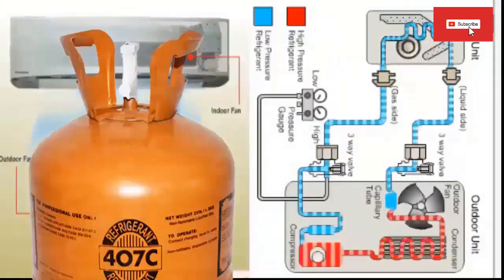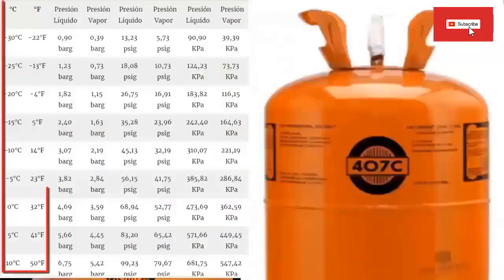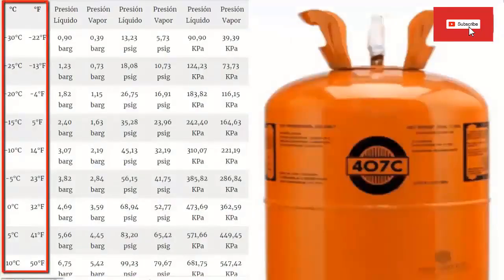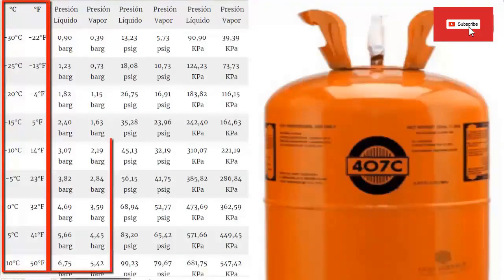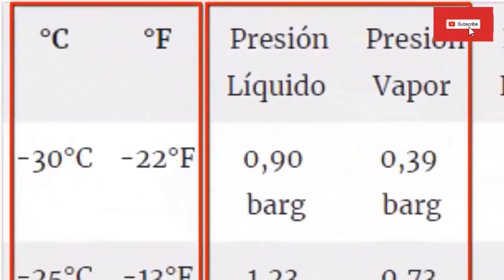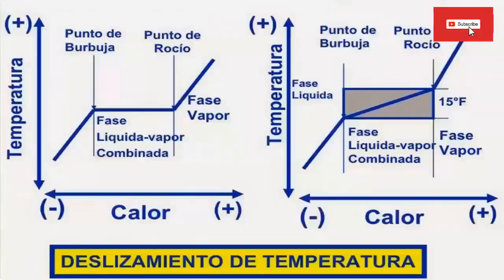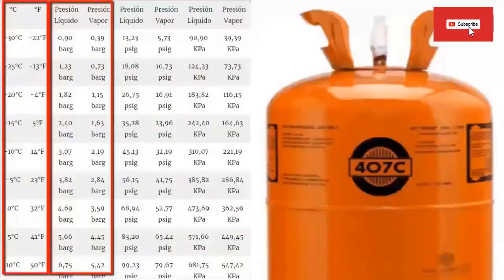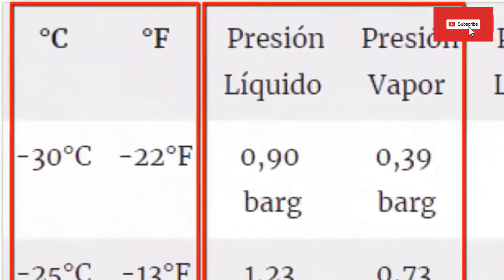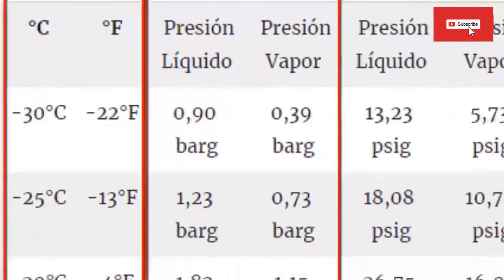Now we focus on the gauge pressures of R-407C in an air conditioner. In the table, the first column shows the saturation temperature, followed by the bubble or liquid pressure, and then the vapor or dew pressure. There are two types of pressures because R-407C has glide, meaning the temperature of its transformation from liquid to vapor — or vapor to liquid — does not remain constant. In a zeotropic mixture, the change of state of the most volatile compounds occurs first, causing the temperature to increase throughout the phase change until evaporation occurs entirely.